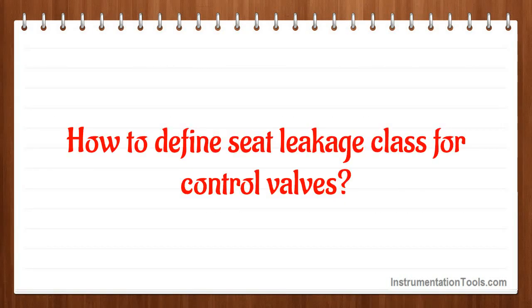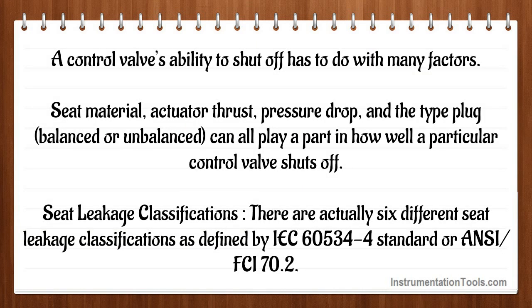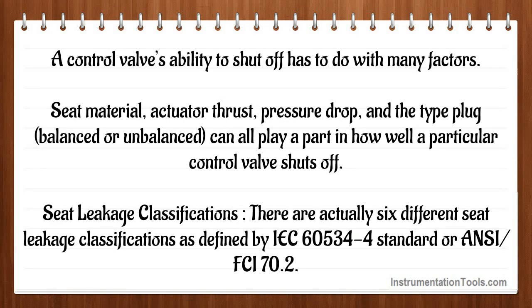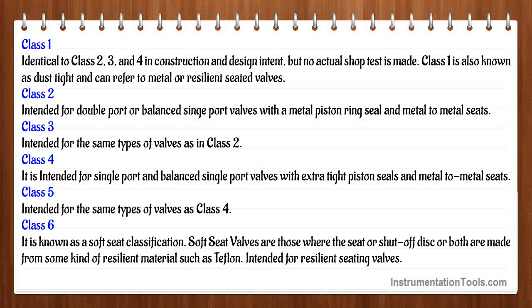How to define seat leakage class for control valves? A control valve's ability to shut off depends on many factors: seat material, actuator thrust, pressure drop, and the plug type — balanced or unbalanced. There are six different seat leakage classifications as defined by IEC 60534-4 standard or ANSI/FCI 70.2. Class 1 is identical to Classes 2, 3, and 4 in construction and design intent but no actual shop test is made. Class 1 is also known as dust tight and can refer to metal or resilient seated valves.